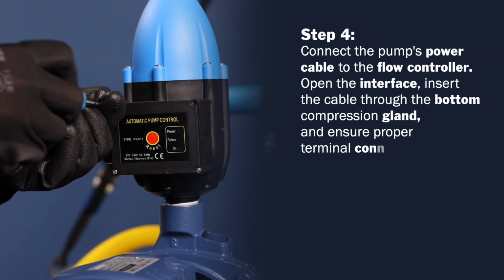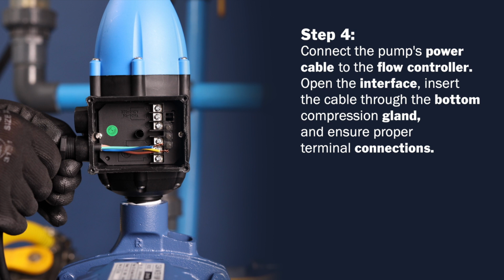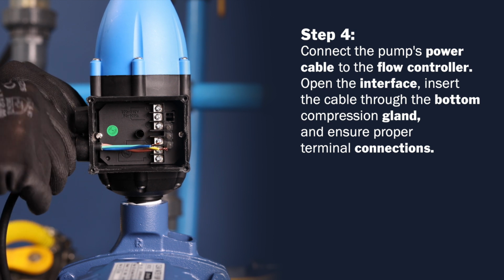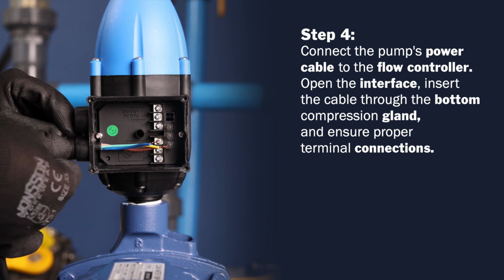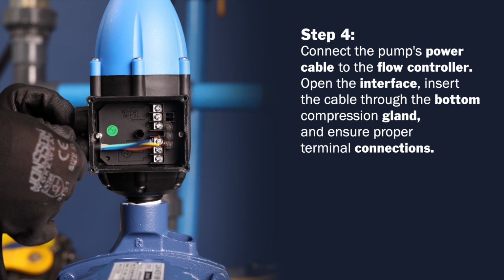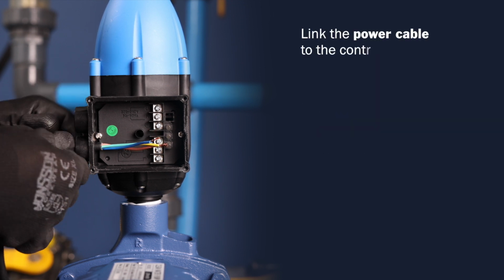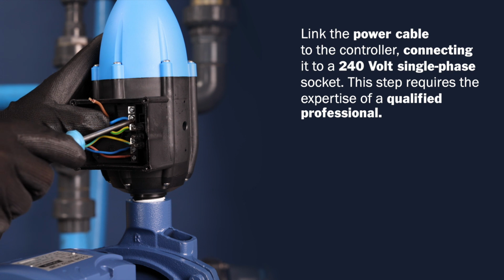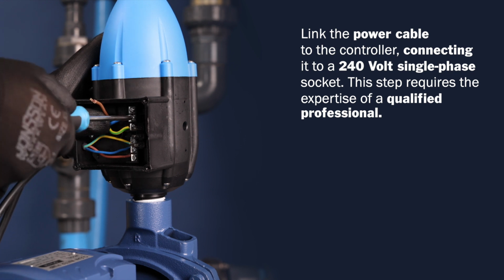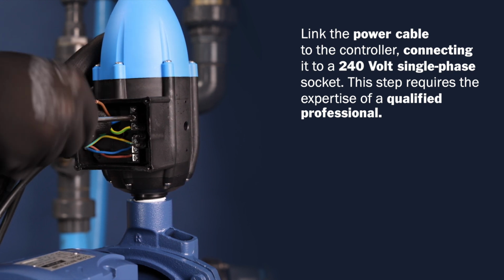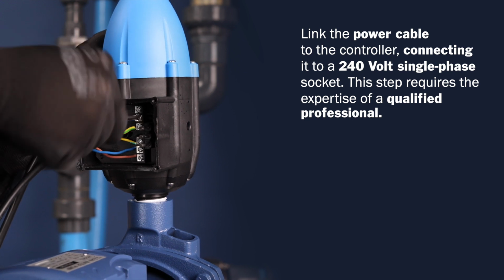Step 4. Connect the pump's power cable to the flow controller. Open the interface. Insert the cable through the bottom compression gland and ensure proper terminal connections. Link the power cable to the controller, connecting it to a 240-volt single-phase socket. This step requires the expertise of a qualified professional.